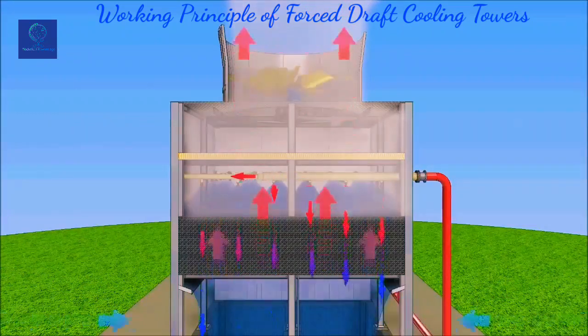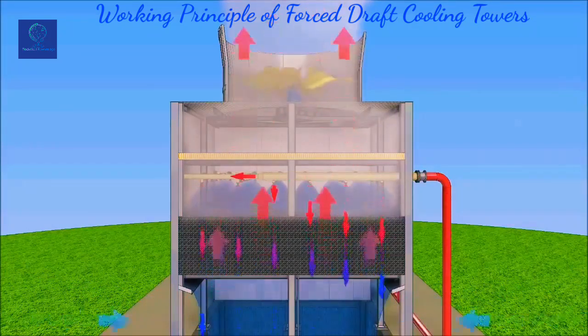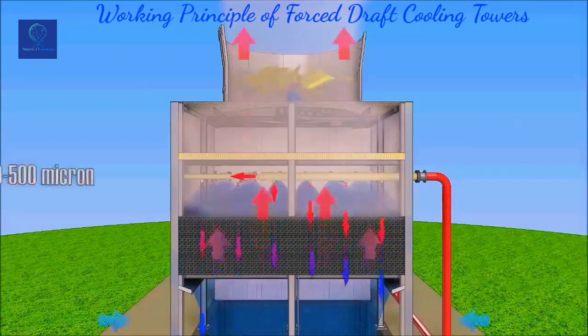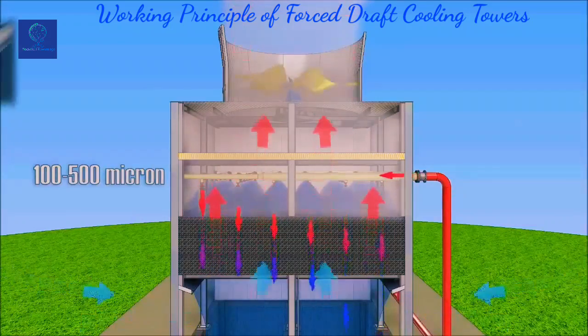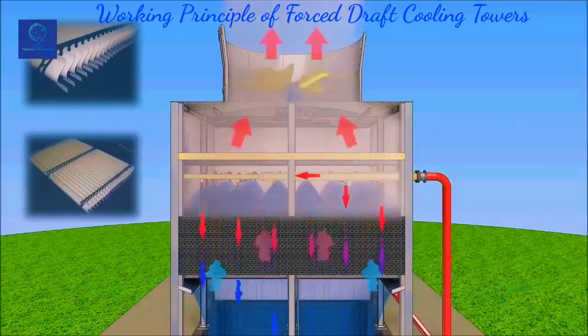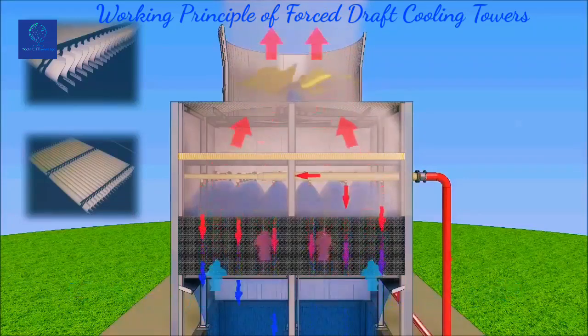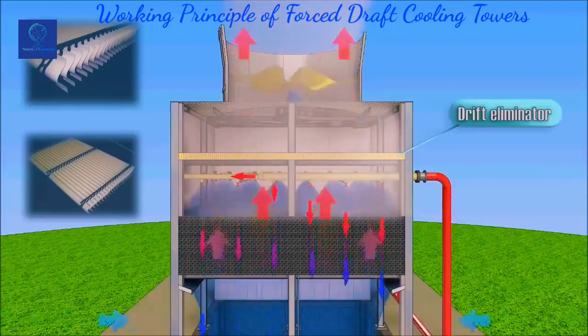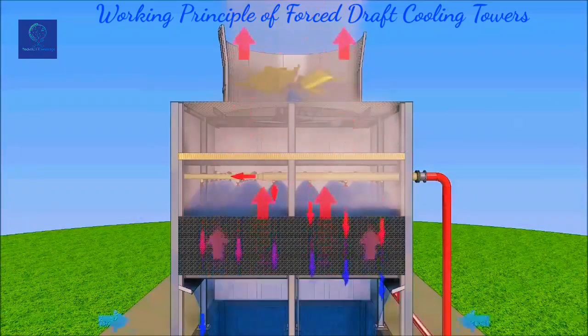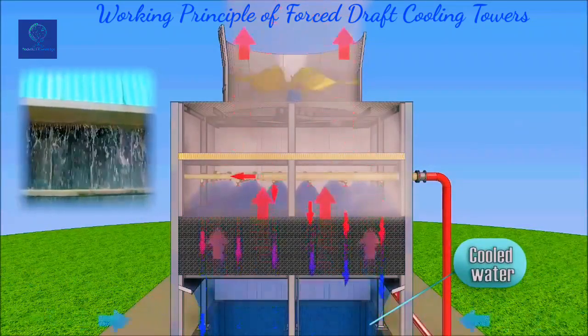Operating a cooling tower emits air saturated with water vapor and containing water droplets with a size of 100–500 microns. To prevent entrainment of water droplets, a drift eliminator is installed above the water distribution system. Cooling water moves down and flows into a catchment tank, from which a pump supplies it to the process technology.